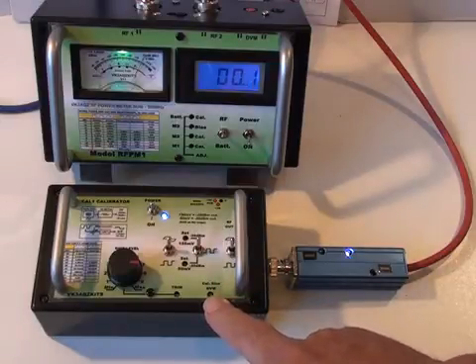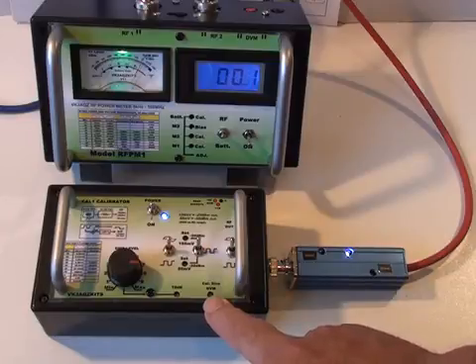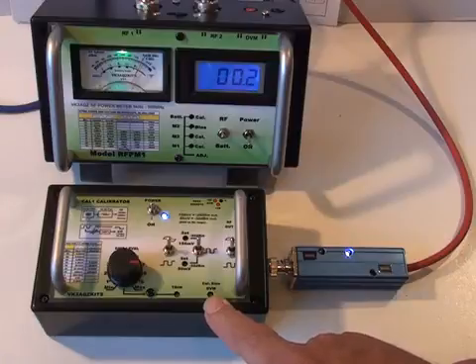If any of the signals through the attenuator, any of the harmonics, are able to bypass some of the padding, then your attenuator will not give the correct answers with this particular detector head.